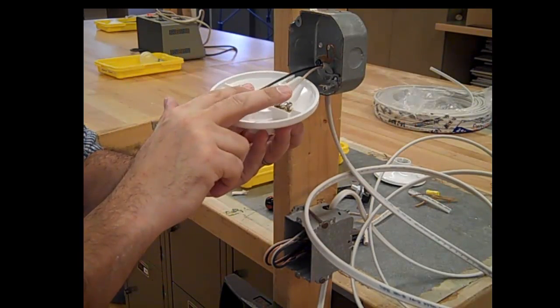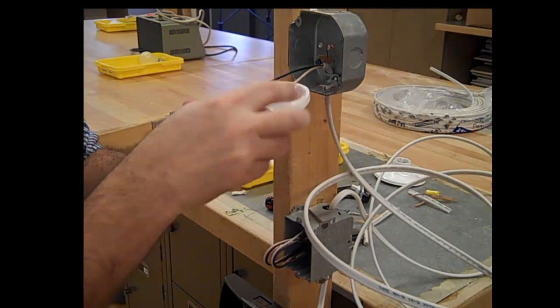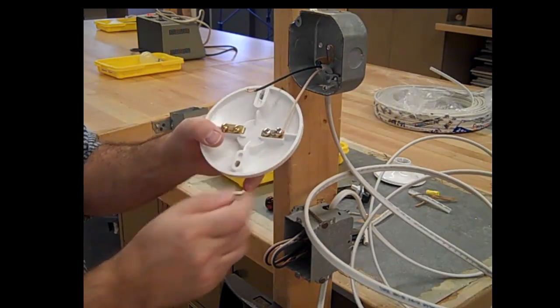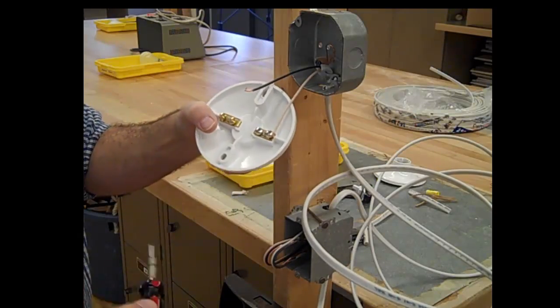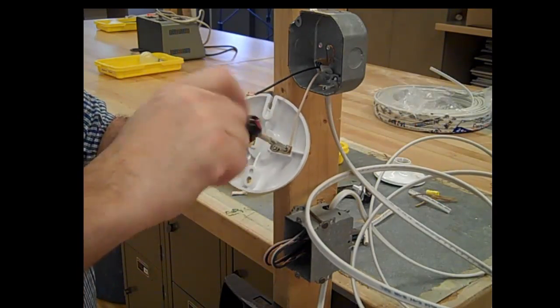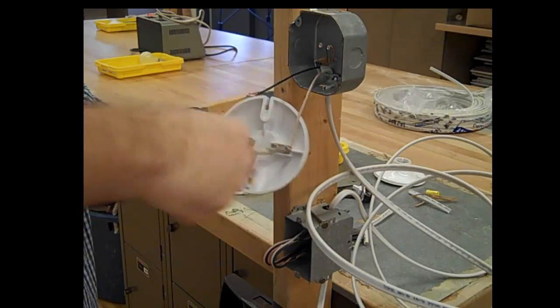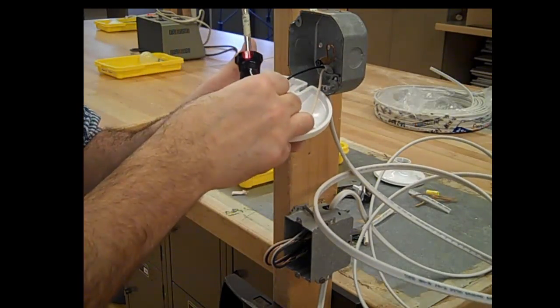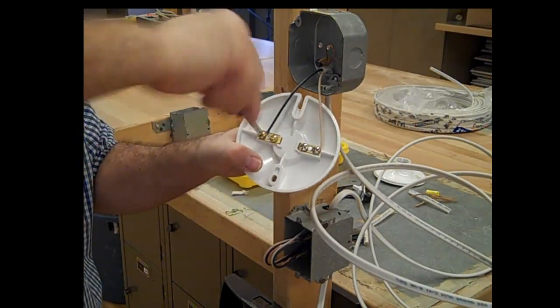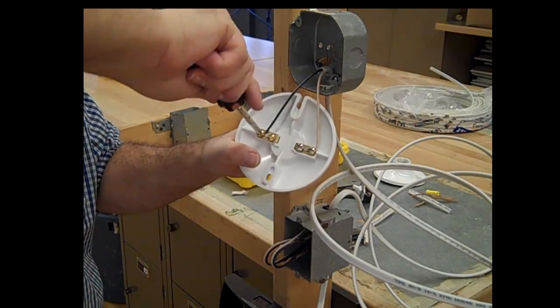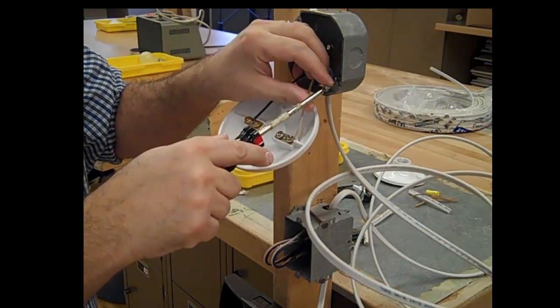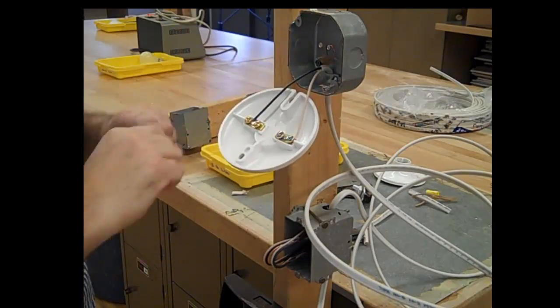Black to brass, white to silver. Silver is lighter, brighter, and wider than brass. Black is darker, brass - B&B - all different types of ways to remember where these go. White goes to silver chrome, and I can tighten that screw. Black goes to brass, tighten that screw.